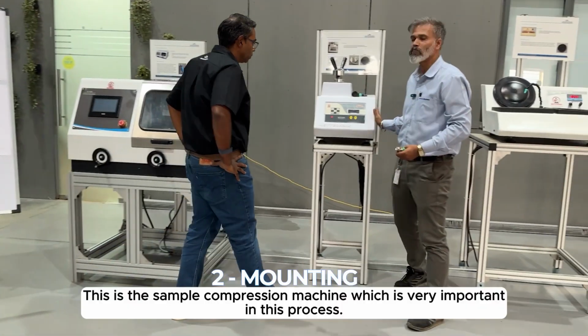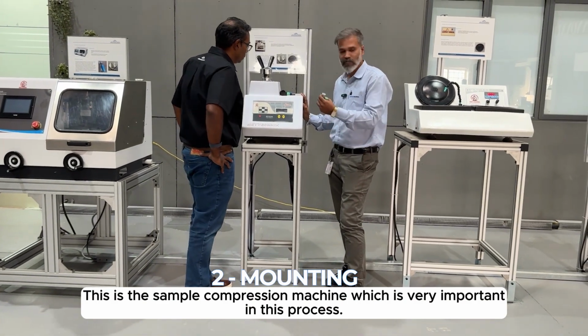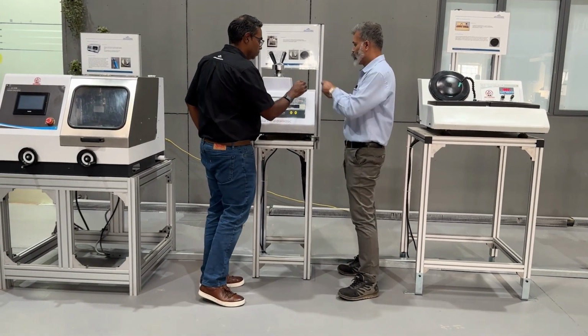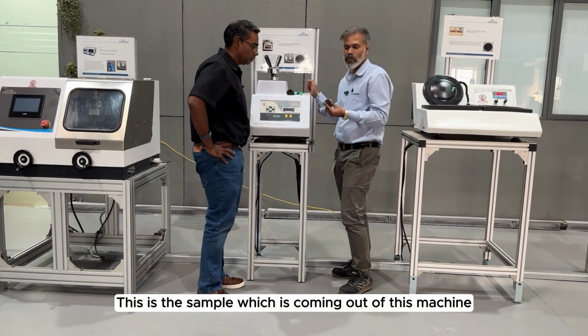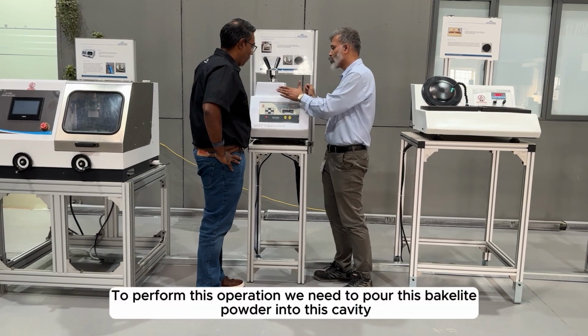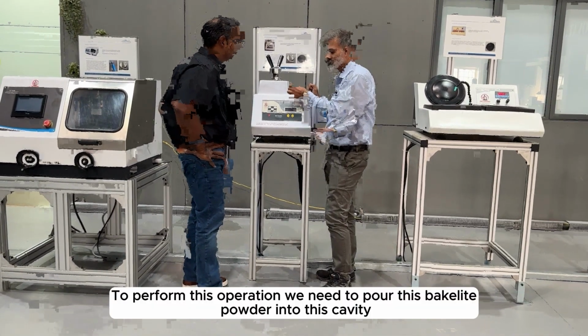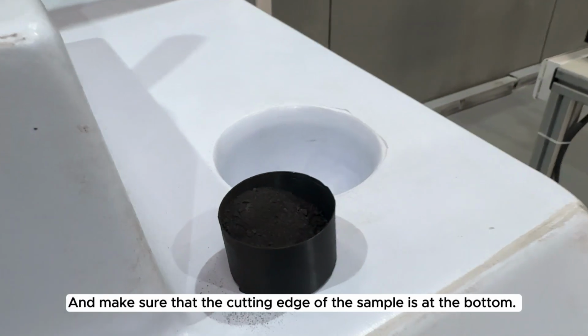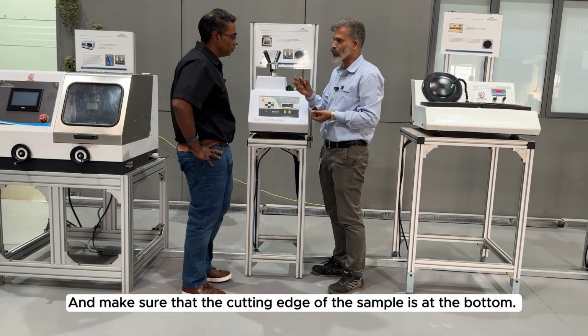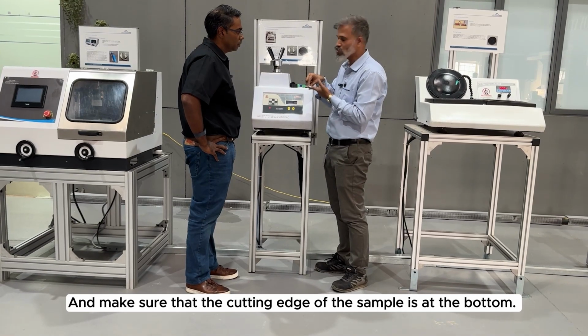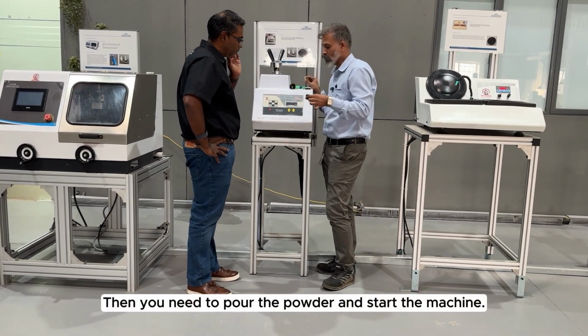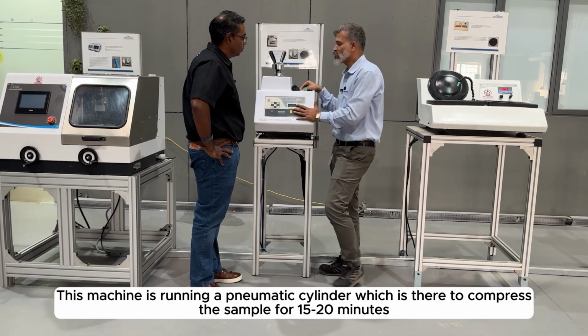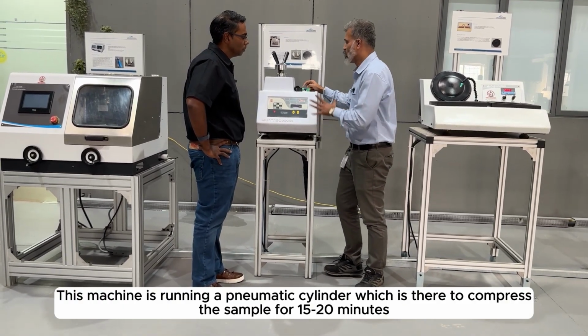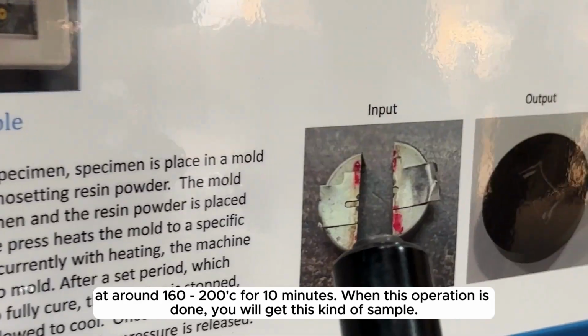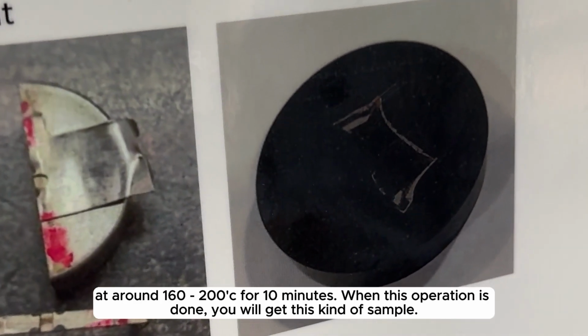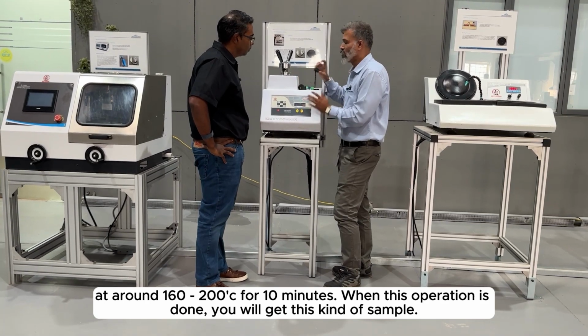Right. And this is the sample preparation machine, which is very important in this process of the laser weld depth penetration validation. This is a sample which is coming out of this machine, but to perform this operation, we need to pour this powder. This is the Bakelite powder. We need to pour it in this cavity and make sure that the cutting sample we have just got from the cutting machine is put with the cutting edge at the bottom, and then you pour the powder. Once you start this machine, it has a hot pneumatic cylinder, which heats to around 160 to 200 degrees Celsius for 10 minutes. And once this machine operation is done, we have this kind of sample.